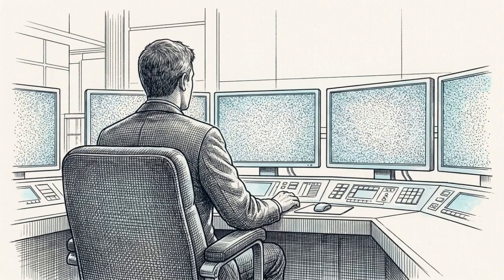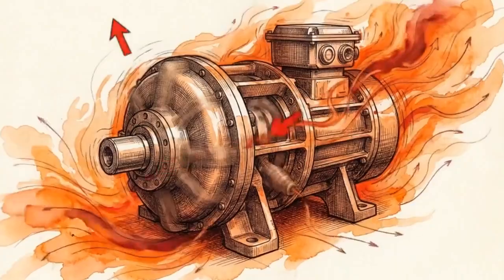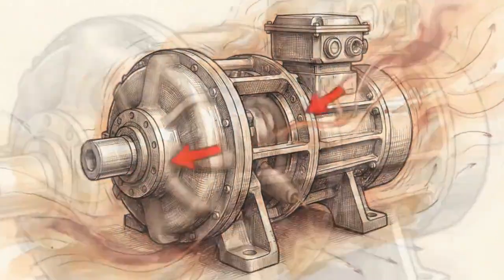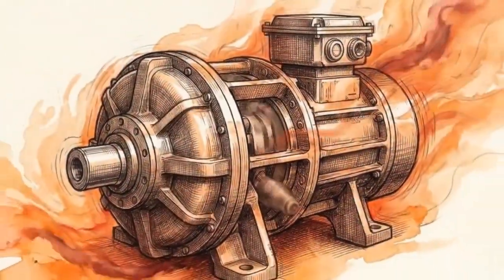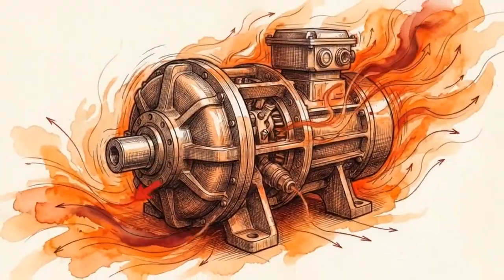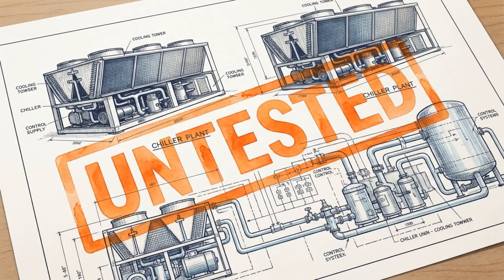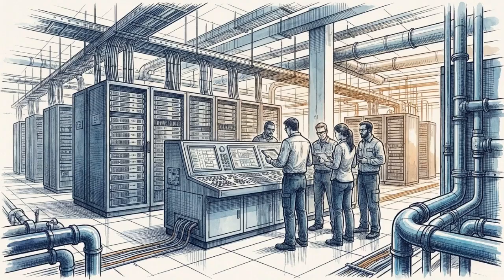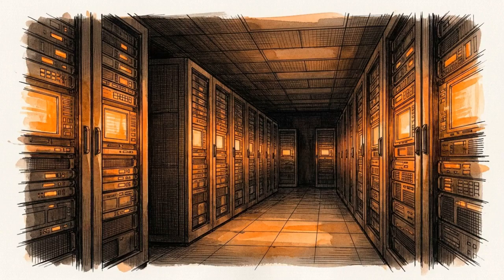Without synchronized thermal telemetry, facility operators are flying blind. They are forced to assume the plant is absorbing heat when the equipment might just be spinning its compressors without transferring any real energy. Theoretical design margins mean nothing until they are tested. The ultimate proof of the recovery sequence is the Integrated System Test, or IST, which simulates a complete black start blackout while the facility is under a representative IT heat load.